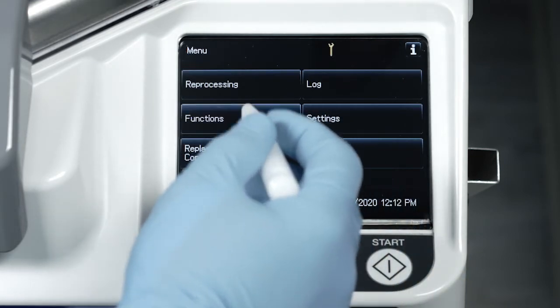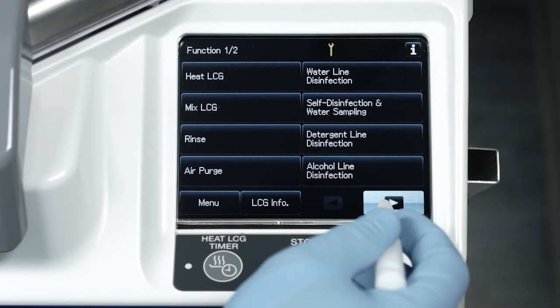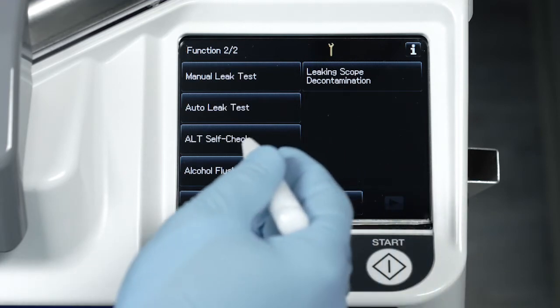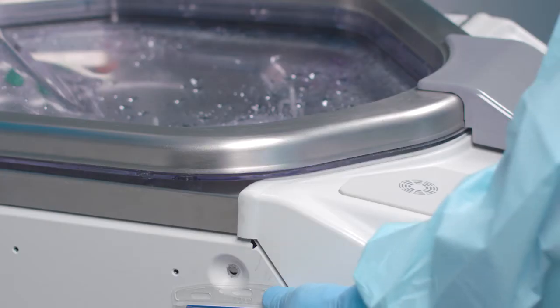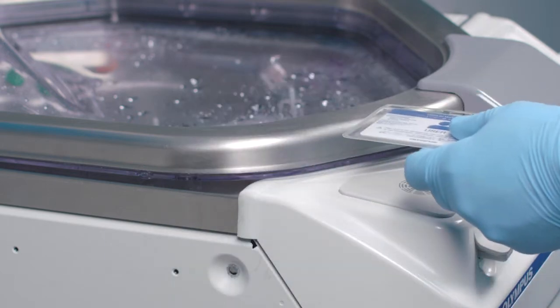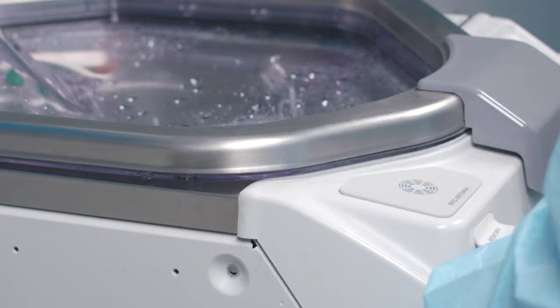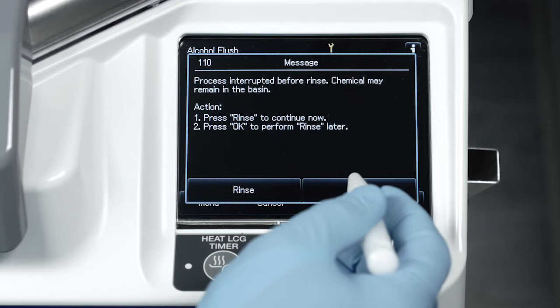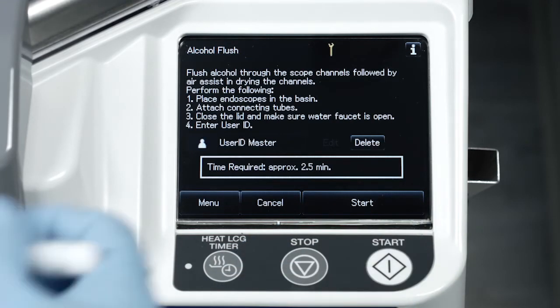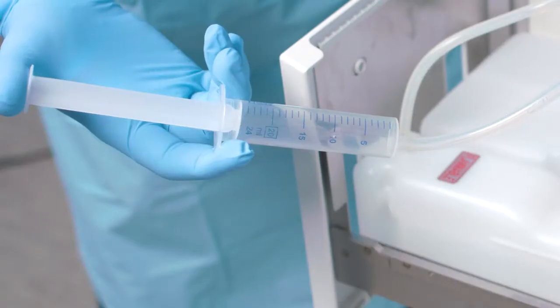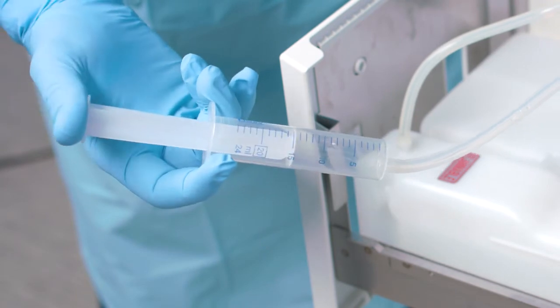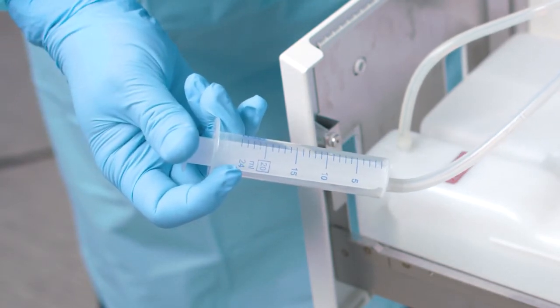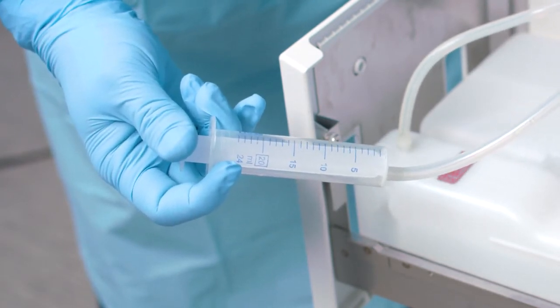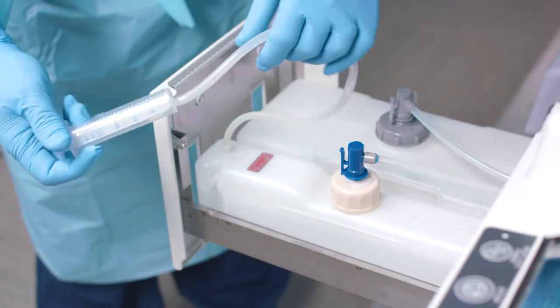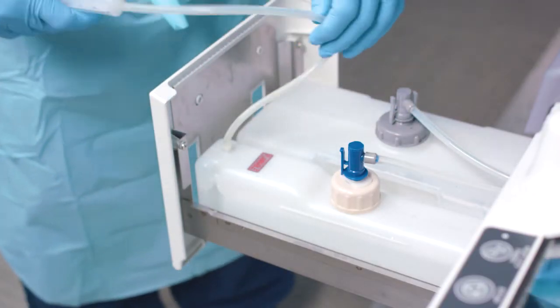Now, go to the function menu. On the second page, select Alcohol Flush. Then, scan the user ID on the OER-Elite RFID reader. Press the OK button. Press the Start button. Flush the air in the syringe by pressing the plunger the full length of the barrel within 30 seconds. Perform the flush again if necessary.